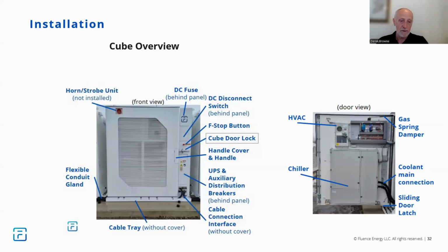If you look at the left-hand photo in the bottom left, we've got a flexible conduit which allows all the cables to interconnect the line of cubes. We've got a strobe unit to indicate if there's a fire or overheating within the cabinet itself, and it helps firefighters and operators to pinpoint the exact location of the cube. Each cube is fused with physical fuses for protection and a disconnect switch allowing maintenance or isolation of that particular cube.